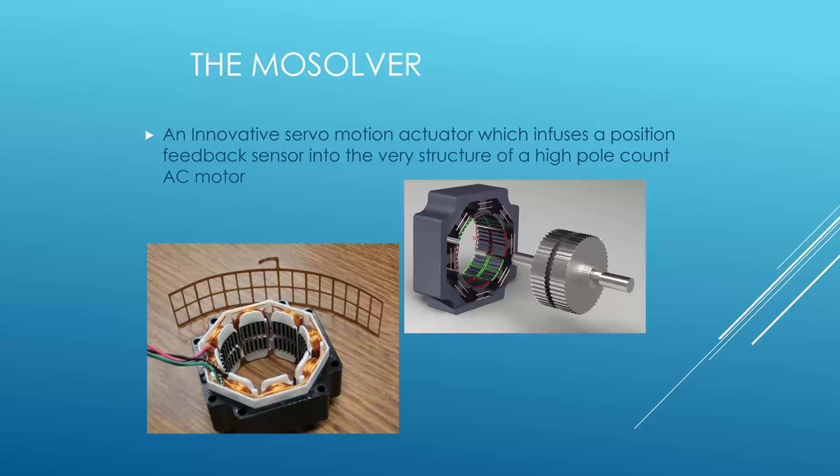Let me answer a question here. With inertia mismatch, is there a drawback on energy efficiency and accuracy? There's sometimes a limit. If you have too high of a mismatch, you may have a hard time getting the power into the system, so you may need some gearing, but we can get away with a lot less gearing. Often a tooth belt is sufficient instead of a gearhead. It has very long life, a lot of damping, and doesn't degrade in the same way as gearheads, which wear and start getting a lot of backlash and issues.